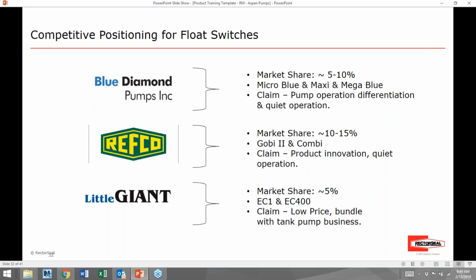Blue Diamond is also a relative newcomer to the pump market. They have about 10 to 15% of the share, and they came on the market with their Maxi and their Mega Blue. You saw the Maxi Blue on that picture at the Kroger grocery store on that Mitsubishi unit. So the Maxi and the Megas are very large pumps. They're very heavy, and they're not suitable at all for residential applications. Their newer pump is the Micro Blue, which was developed to compete with the Mini Aqua pump.